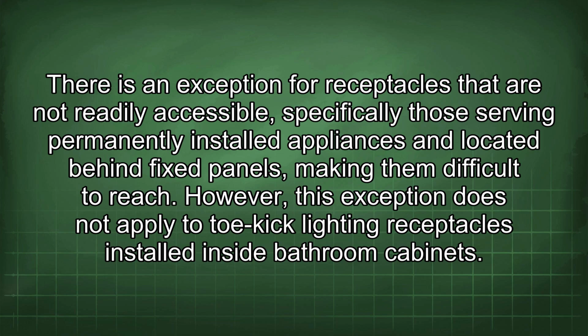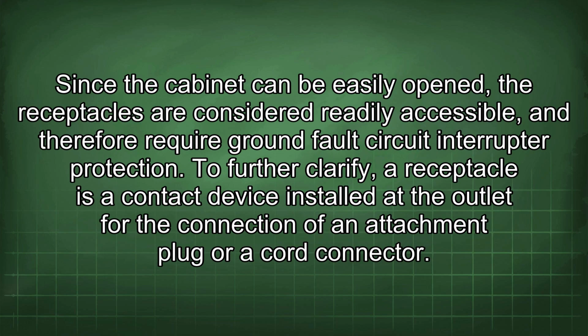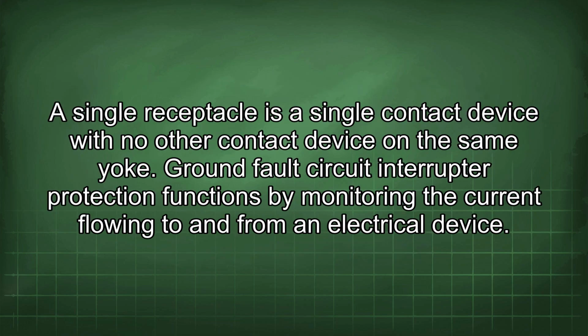However, this exception does not apply to toe kick lighting receptacles installed inside bathroom cabinets. Since a cabinet can be easily opened, the receptacles are considered readily accessible and therefore require ground fault circuit interrupter protection. To further clarify, a receptacle is a contact device installed at the outlet for the connection of an attachment plug or a cord connector. A single receptacle is a single contact device with no other contact device in the same yoke.